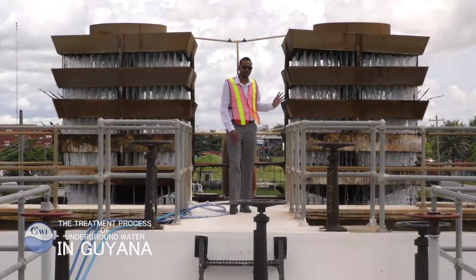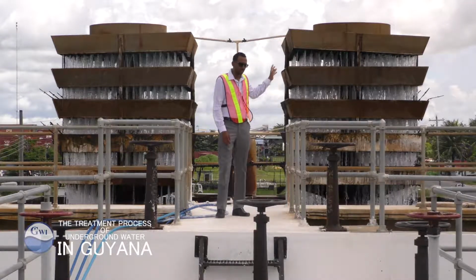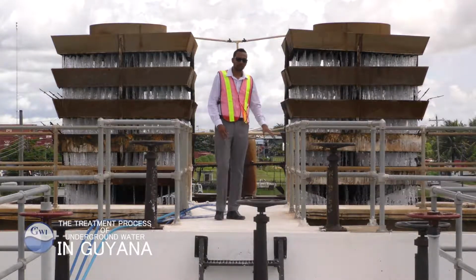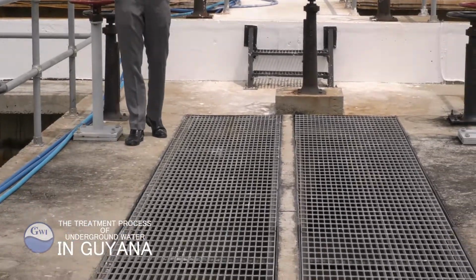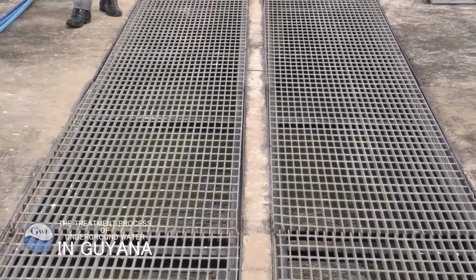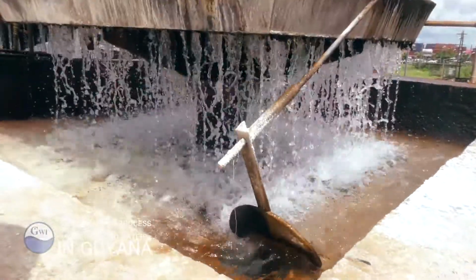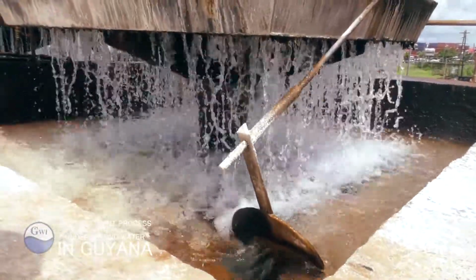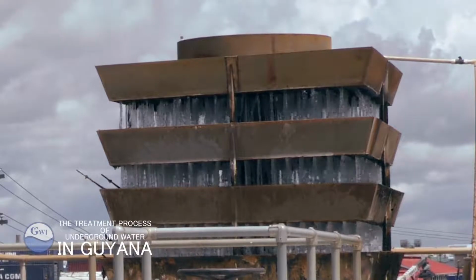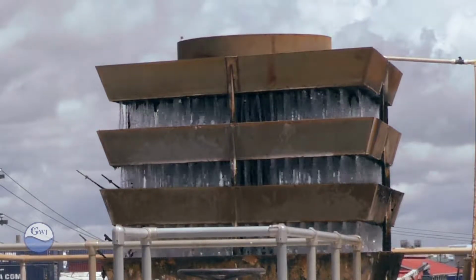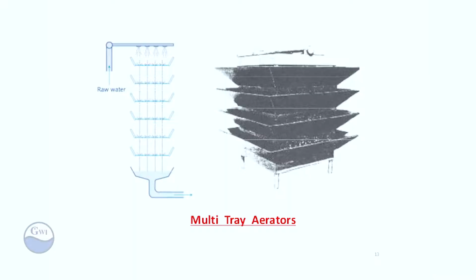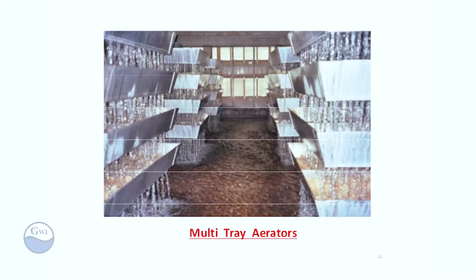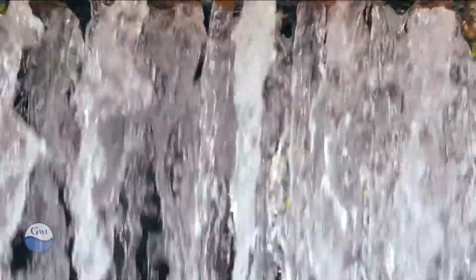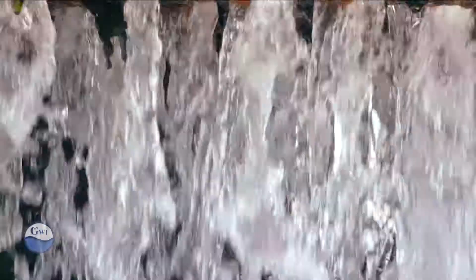For that, the aerators are used. These take advantage of the abundance of oxygen that is present in the atmosphere, which converts the clear water iron to the red water iron. The most commonly employed aerator type is the multiple tray aerator. This entails the exposure of the water in thin films, created as it flows through the various trays, which allows for oxidation or transfer of the ferrous, also known as clear water iron, to the insoluble, or ferric iron, which then precipitates to the iron hydroxide, which can be physically removed.